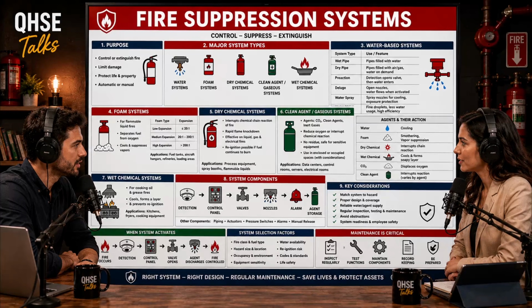Yeah. How do you stop something that literally feeds on water? You have to use special extinguishing agents specifically rated for the metal involved, mostly proprietary dry powder agents, and note that it's dry powder, not dry chemical, which is for B and C. Huh, good distinction. Yeah. There are also some non-proprietary agents like completely dry sand or sodium chloride. They work by completely encasing the burning metal, isolating it from oxygen, and acting as a massive heat sink.